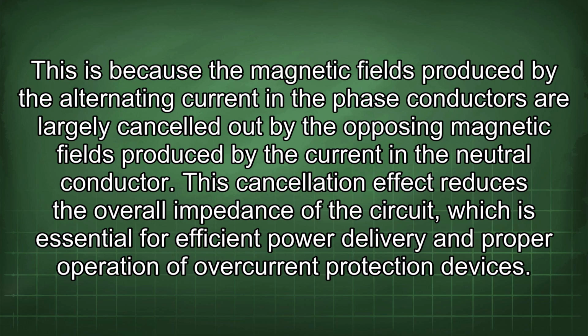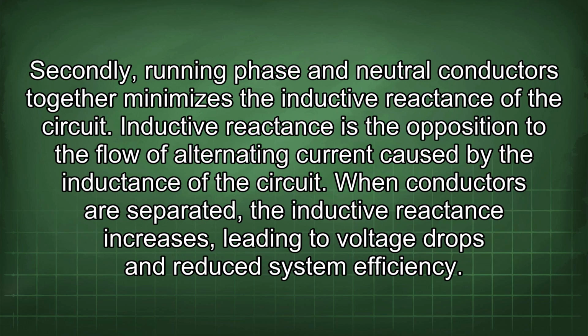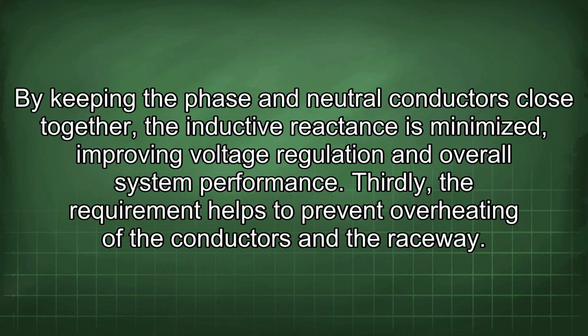of overcurrent protection devices. Secondly, running phase and neutral conductors together minimizes the inductive reactance of the circuit. Inductive reactance is the opposition to the flow of alternating current caused by the inductance of the circuit. When conductors are separated, the inductive reactance increases, leading to voltage drops and reduced system efficiency.